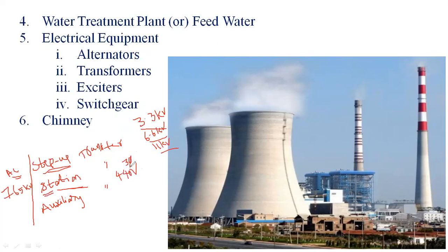Actually, the station transformer's capacity is 11 kV. These 3.3 kV, 6.6 kV or 11 kV are stepped down to 440 volts, that is, a three-phase, three-wire system or a three-phase, four-wire system. In the power plant, the supply is used for lighting purposes, and the remainder for motors, drinking water, charging batteries, charging mobiles, fans, office AC, refrigerators and so on.